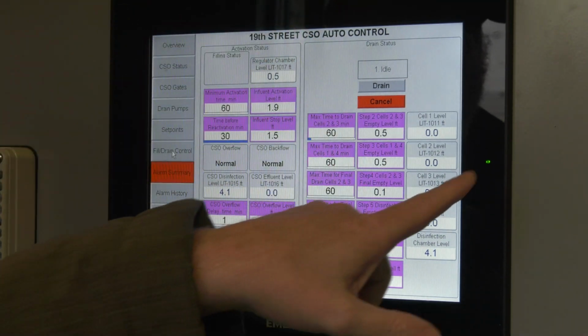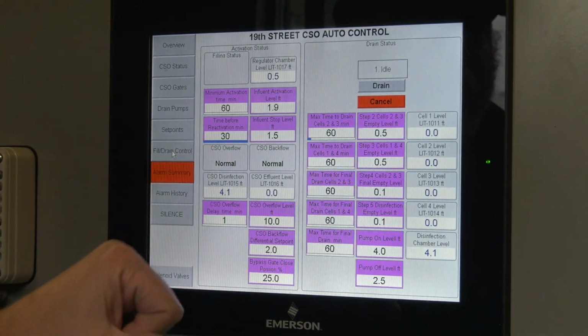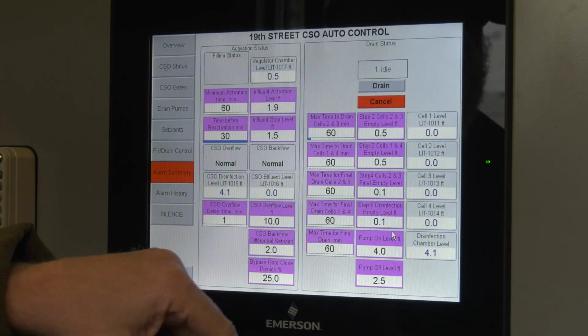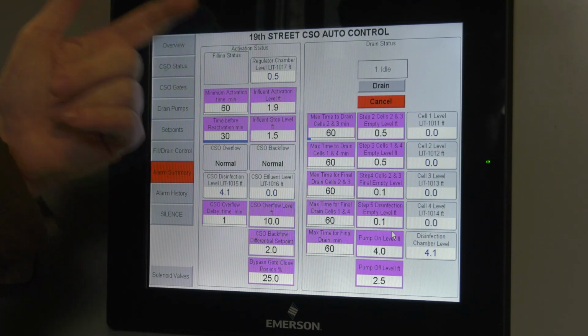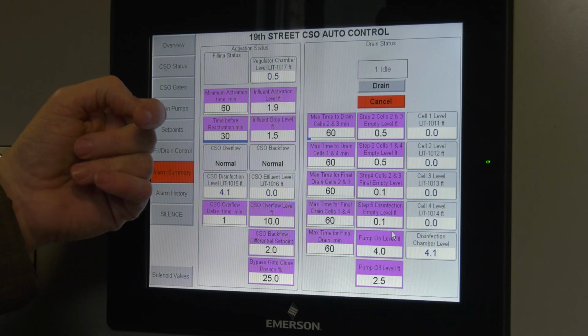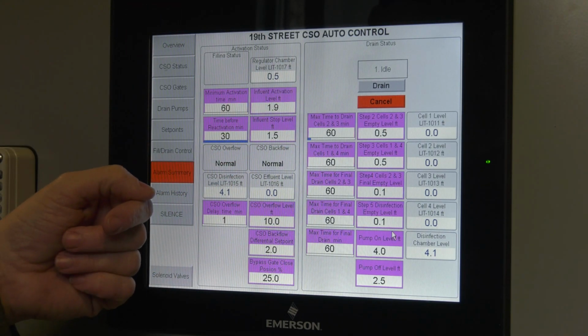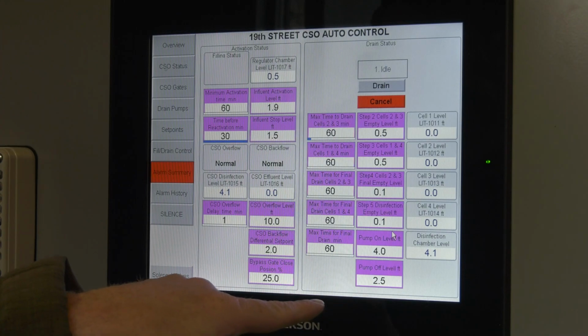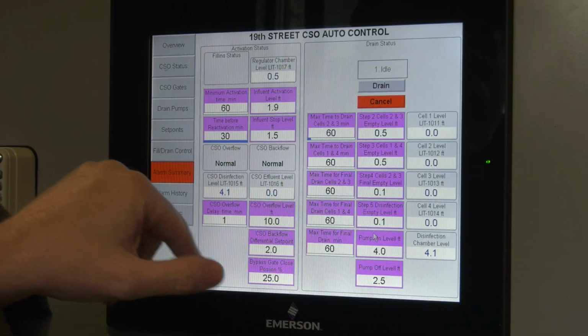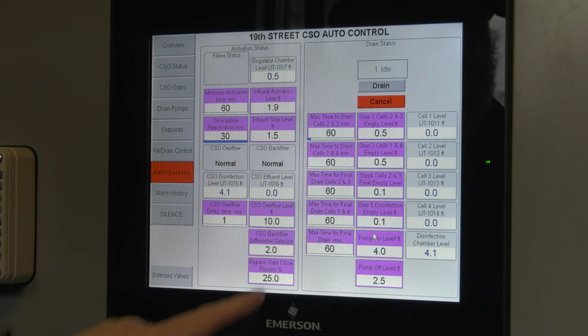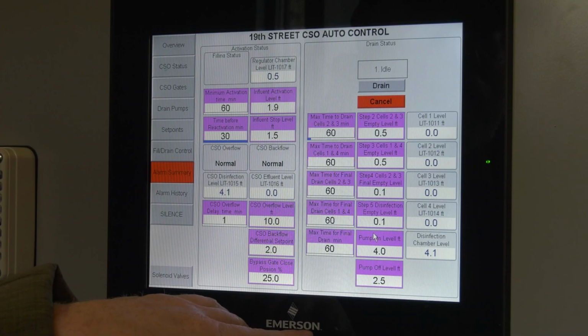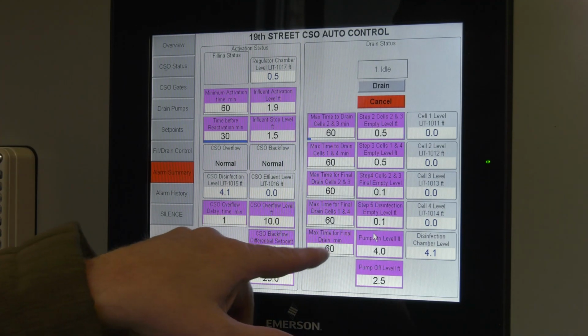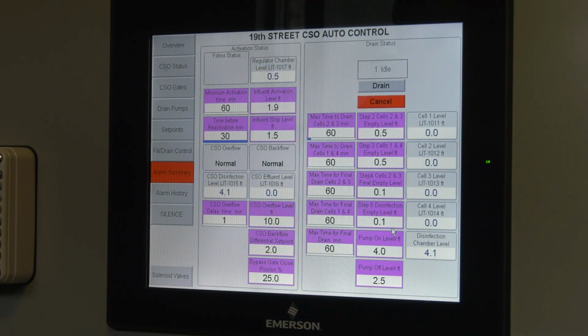It looks at each cell level individually. When the cell level is less than the operator adjustable set point, or it's been 60 minutes, which is also operator adjustable, it'll move to the next cell, and it opens the drain gate for each of the 4 cells. When the disinfection level is less than the operator adjustable empty level or operator adjustable time, 60 minutes, it'll stop the drain cycle. And the drain cycle can't be repeated until the operator adjustable max drain time has been exceeded.